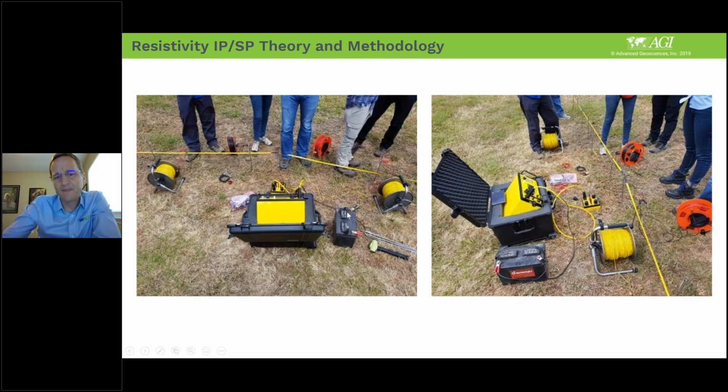There could be something conductive coming out of it, fluids, and that would cause a ground loop. The negative post is actually a reference for all these measurements. So you don't want anything else connected to your battery or any kind of conductive fluids leaking out or possibly conducting some stray current into the ground.